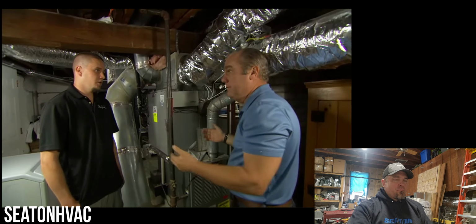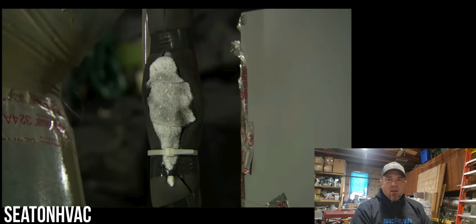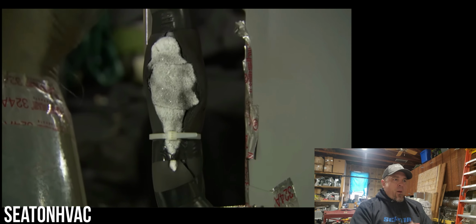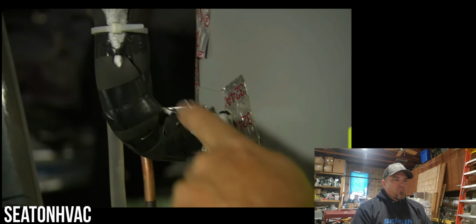Okay. So it's pretty obvious by looking at that, you know, they retrofitted the AC in after, and that coil's not put in properly. It's not the same width as the furnace, and then in doing so, you can tell they reconfigured some of that ductwork, because originally it was most likely metal rigid duct, and then there you see the flex tapping off now. So it was a total redo. It looks like they just scabbed it in though. That's actually starting to form ice right now. So that's on the line sets that go to outside, and I imagine on the coil too.